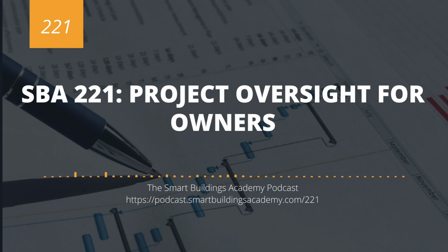I've seen it at some of the most renowned airports and data centers and hospitals in the world, where they had these really awesome interoperability use cases. They did not properly explain the purpose, the business value, and how to operate this to the operational team. Warranty phase came and went. They decided to no longer continue a service contract with the controls contractor. And as soon as an API changed or there was a version update that broke the integration, rather than figuring out why that's not working and getting that integration to work again, guess what? It got put in hand. And that is just the reality of the world we live in. So if you want to ensure that interoperability continues, and maybe that's just simply aligning to building automation integration.